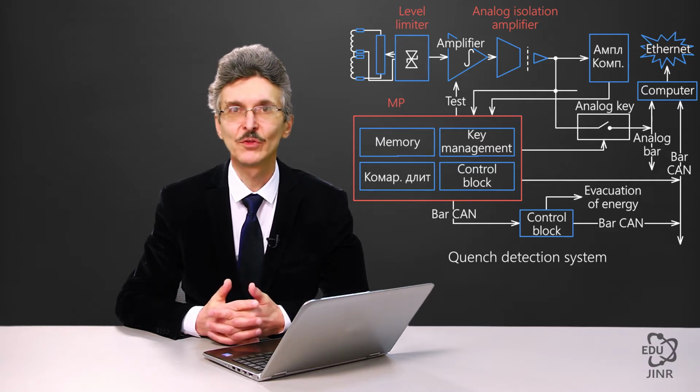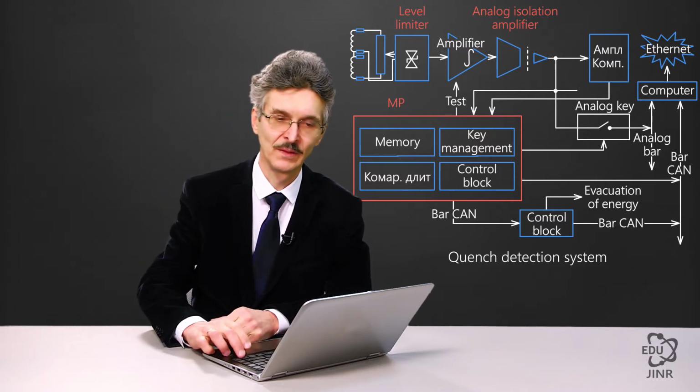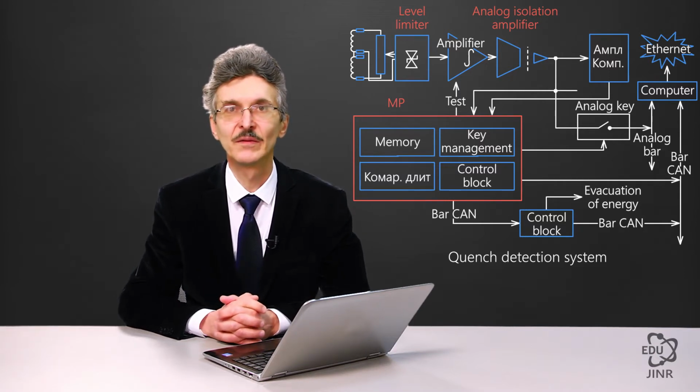It is also protected by group detectors. There are few magnets that don't have a pair. To protect these magnets, a potential output of energy in the middle point of the coil is used. The bridge is formed from two halves of the coil of the same magnet. All these detectors are combined into a main control system, which, in case of a quench, shows the point of origin of the quench and provides insights into its developments.